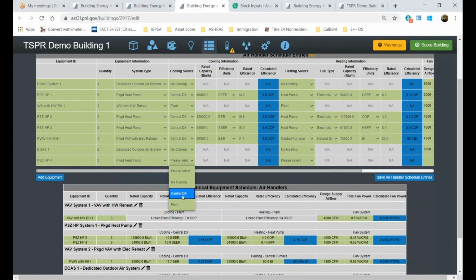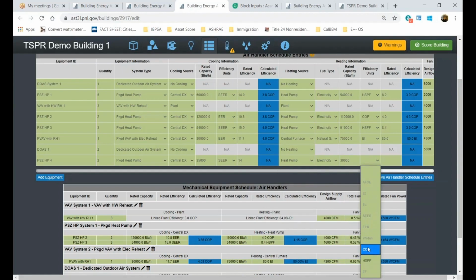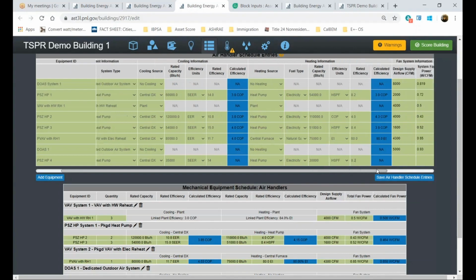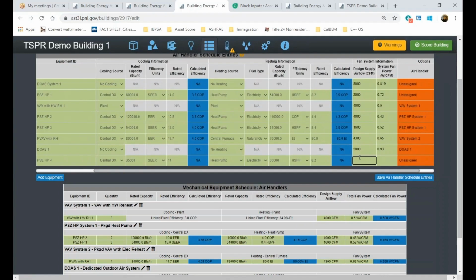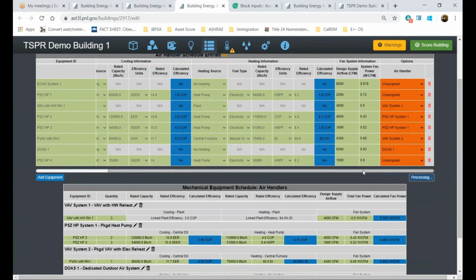Packaged heat pump. Cooling source is DX and heating source is heat pump. And specify a capacity in BTU per hour, and then the efficiency. And for the heat pump, again, I can specify a capacity, rated efficiency, and then the design airflow. So for this, we can specify 1000 CFM with a fan power of 0.6 watts per CFM. And then I can click on Save Air Handler Schedule Entries.